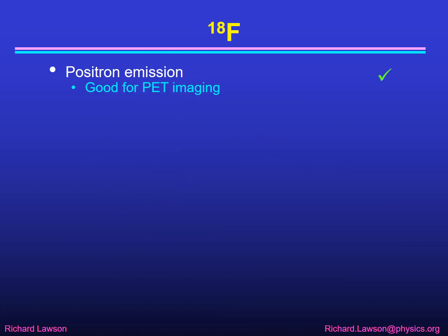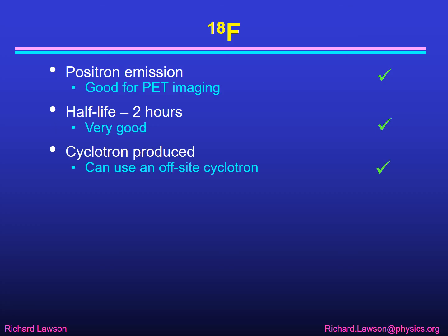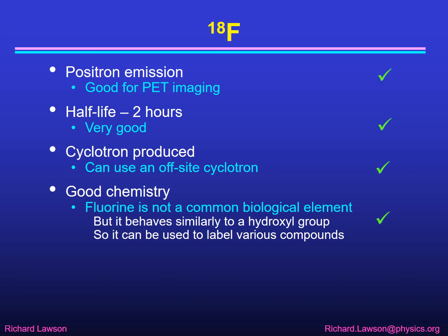Fluorine-18 is another radionuclide that decays by positron emission, so it is also good for PET — positron emission tomography. It's got a half-life of two hours which is very good because it means we can get away with an off-site cyclotron; as long as you've got a cyclotron within a couple of hours' travelling time you can have fluorine-18 delivered to your hospital without having to have your own cyclotron. It has fairly good chemistry — fluorine is not a common biological element but it behaves similarly to a hydroxyl group, so it can be used to label various compounds.